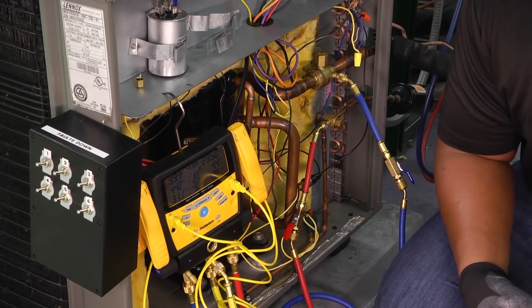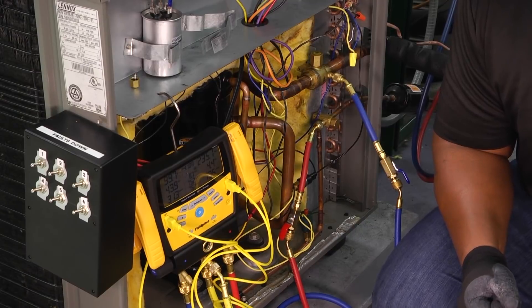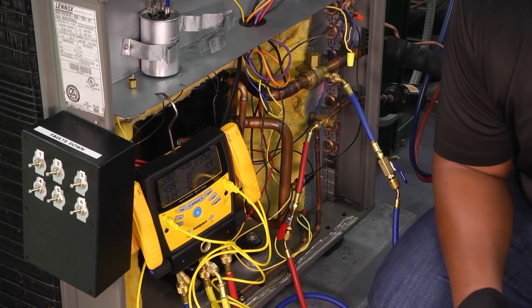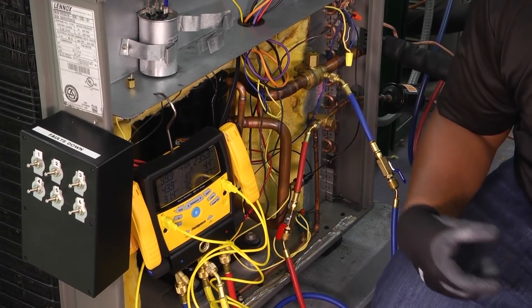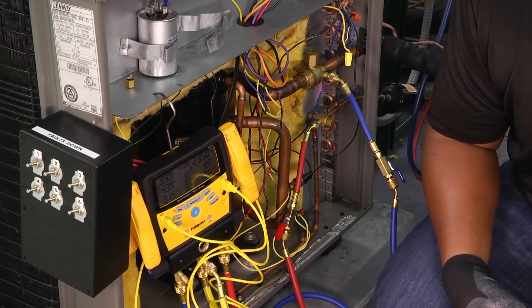If we happen to have a TXV metering device, then we're going to charge our system looking at our subcooling number. Now, it doesn't mean that we totally negate the other number. It just means that that's going to be the primary number that we look at in evaluating the whole system.